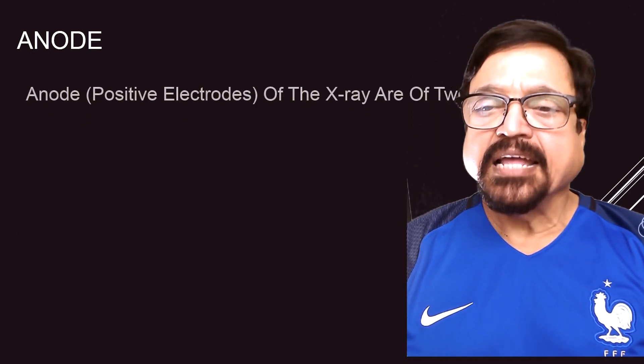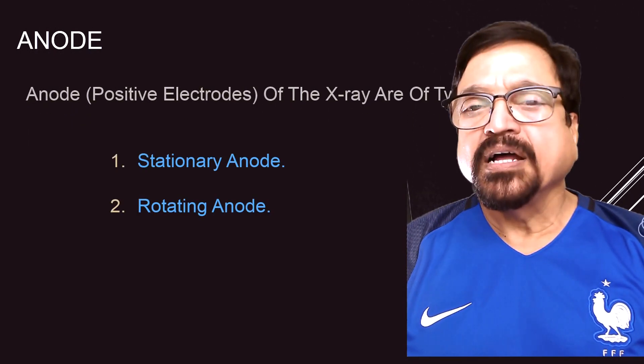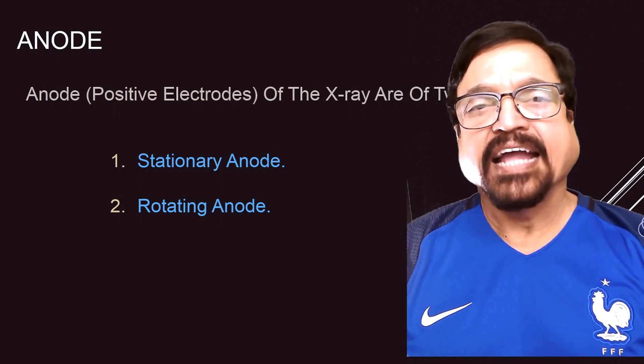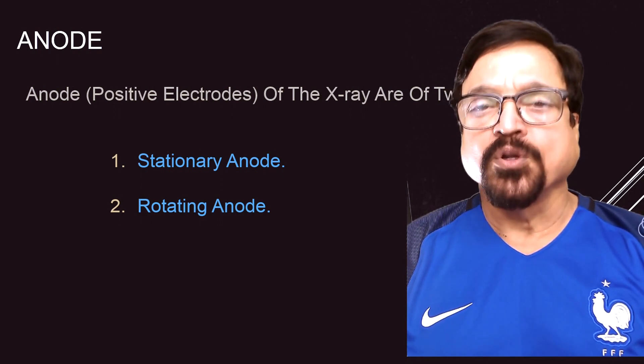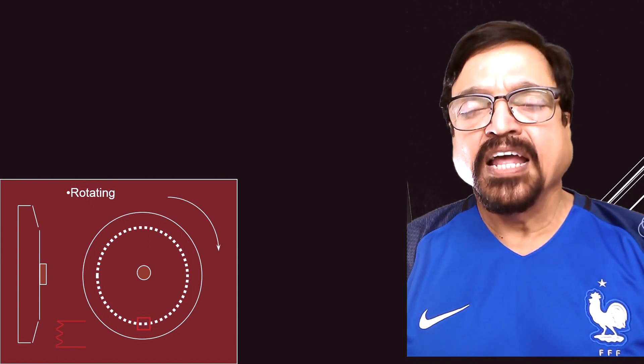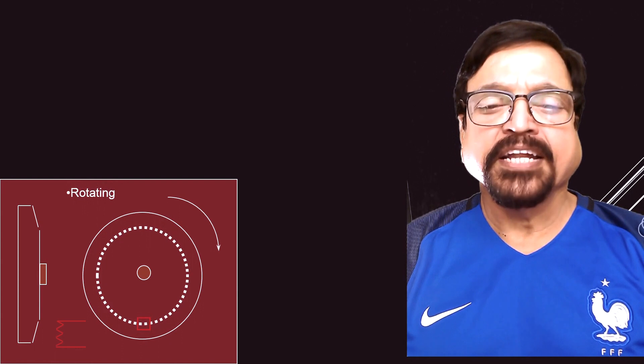Now let's come back to the anode. The anode is positively charged. As far as the anode is concerned, we have either stationary anode or rotating anode tubes. What I am showing you first is a rotating anode — in that the anode rotates at around 3600 revolutions per minute, so it is moving at high speed. It has a focal track of tungsten, and every time a different part of the focal track comes in contact with the electron beam. The advantages of the rotating anode are covered in its dedicated topic.